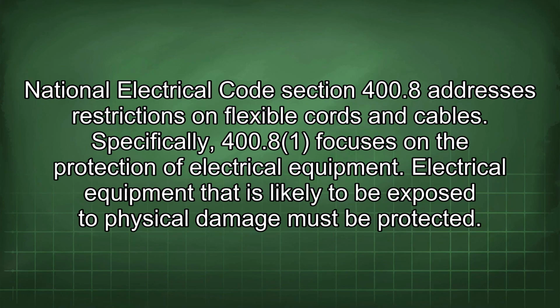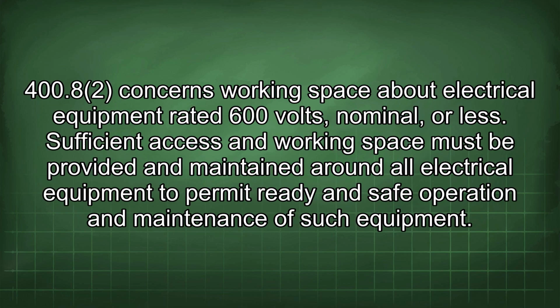National Electrical Code Section 400.8 addresses restrictions on flexible cords and cables. Specifically, 400.8 focuses on the protection of electrical equipment. Electrical equipment that is likely to be exposed to physical damage must be protected. 400.8 concerns working space about electrical equipment rated 600 volts, nominal or less. Sufficient access and working space must be provided and maintained around all electrical equipment to permit ready and safe operation and maintenance of such equipment.